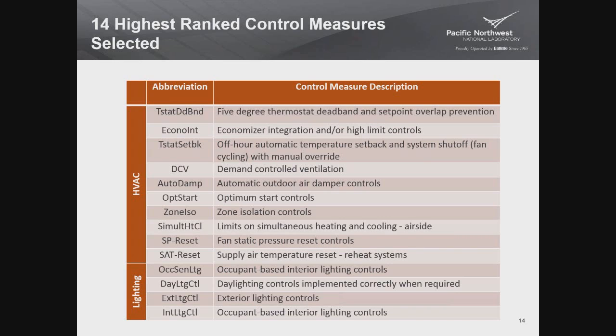The next one, automatic outdoor air damper controls. There's an automatic air damper on air handlers that opens to allow ventilation in there when a space is occupied, closes when the space is not occupied. This requirement is such that when a system goes on to meet a night setback, there's no people in it, but it just gets too cold or too hot at night, that damper has to remain shut. And also during morning warm-up, when you're warming a building up before occupants are there, that automatic damper needs to be shut as well. Optimum start controls.